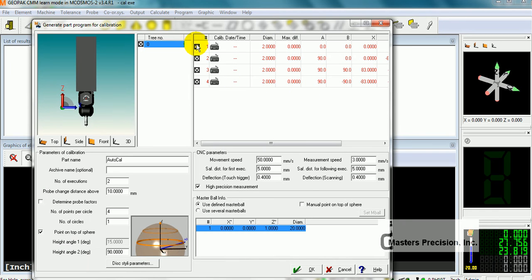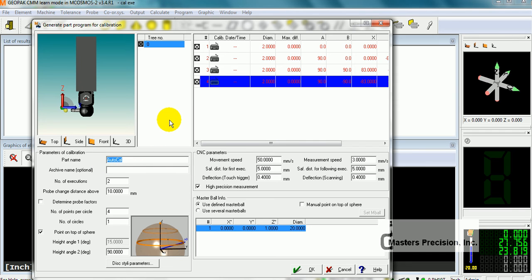As you can see, all the styluses that I have a check mark by them. If I don't want them to be added to the program, I simply click them. Now it adds it back. The part name needs to be changed. I'm going to describe my stylus with this. I'm going to call it 2x20. And then I am going to give the exact same name to the archive. 2x20. It's kind of important that you do the archive probe. The reason for this is you want to be able to recall your probe data in a new program.